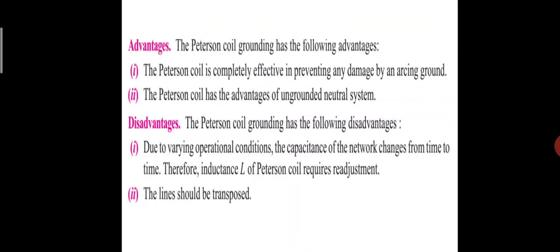Advantages of Peterson coil grounding: The Peterson coil is completely effective in preventing any damage by an arcing ground, and it has the advantages of an ungrounded neutral system. Disadvantages: Due to varying operational conditions, the capacitance of the network changes from time to time; therefore inductance L of the Peterson coil requires readjustment. The line should also be transposed.